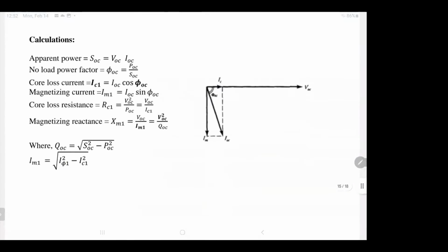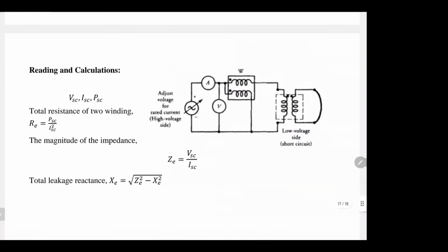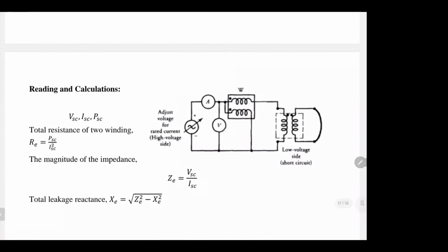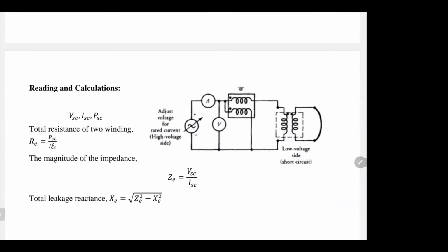The second test is called the short circuit test. In this short circuit test, we flip it. Also, you can do it on either side. You could do the test on the low voltage side or the high voltage side. But in this case, as you see here in this diagram, we make the short circuit on the low voltage side. If you look at this, that's the low voltage side, and the high voltage side is where you put the voltage supply and the measuring instruments.